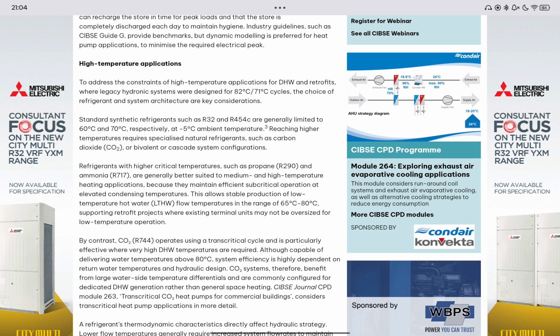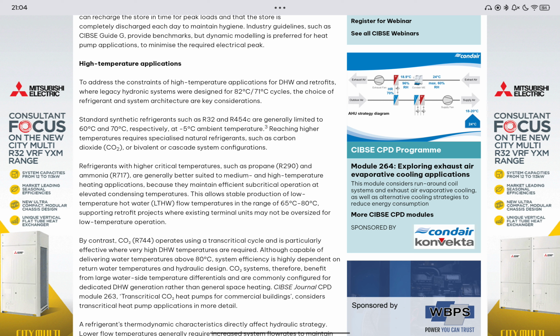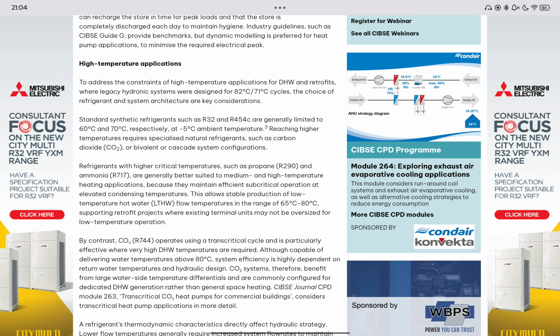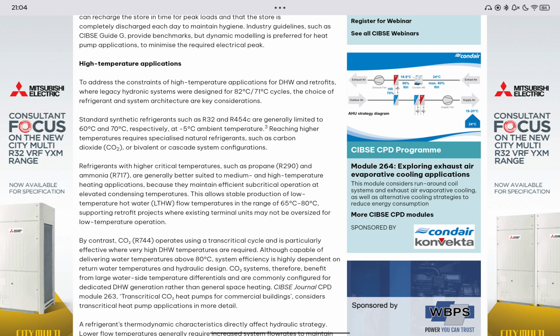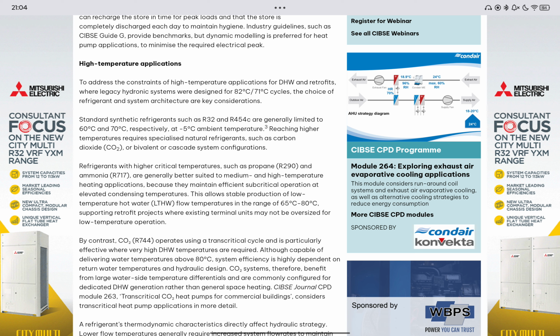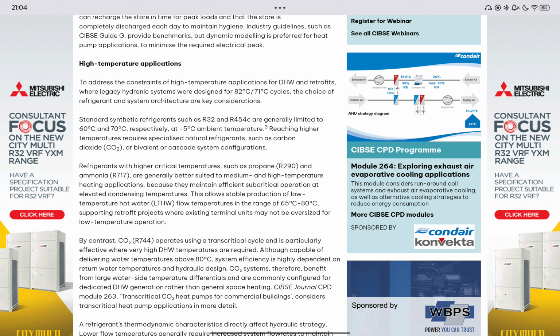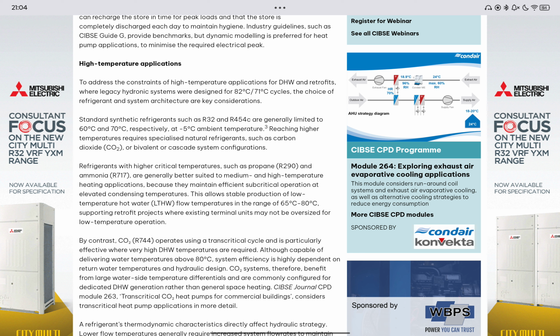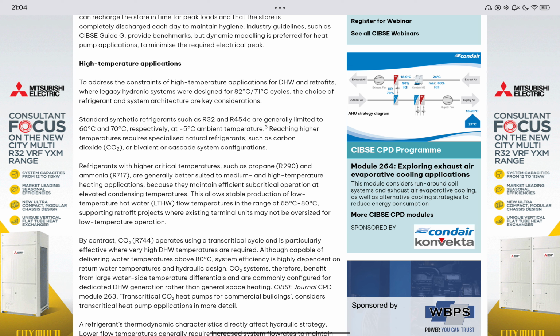To address the constraints of high-temperature applications for DHW and retrofits, where legacy hydronic systems were designed for 82-71 degrees C cycles, the choice of refrigerant and system architecture are key considerations. Standard synthetic refrigerants such as R32 and R454C are generally limited to 60 and 70 degrees C respectively at -5 degrees C ambient temperature. Reaching higher temperatures requires specialized natural refrigerants such as carbon dioxide, or CO2, or bivalent or cascade system configurations.